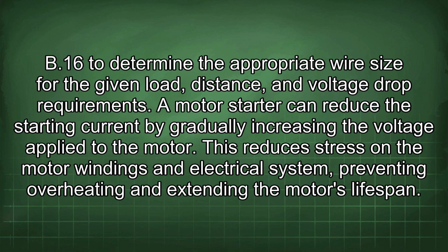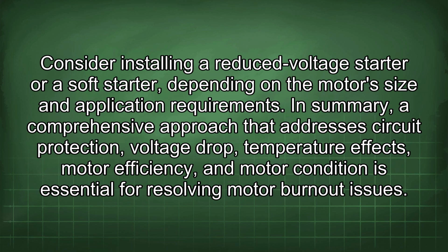A motor starter can reduce the starting current by gradually increasing the voltage applied to the motor. This reduces stress on the motor windings and electrical system, preventing overheating and extending the motor's lifespan. Consider installing a reduced voltage starter or a soft starter depending on the motor's size and application requirements.